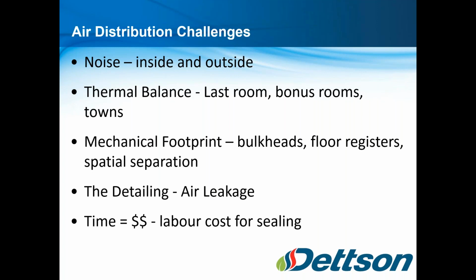So we're building houses better. We can't hear the neighbor mowing their lawn anymore, but you can hear everything cycling inside the house. So we wanted to address noise. We also wanted to address that thermal balance. So how can we utilize the system, the modulating system, and get even better throw and better mix in the home? And we wanted to look at mechanical footprint. So could we reduce some bulkheads, get rid of some floor registers, look at spatial separation and the noise, one, the noise for spatial separation, and two, the mechanical footprint for mechanical separation in smaller square footage developments.